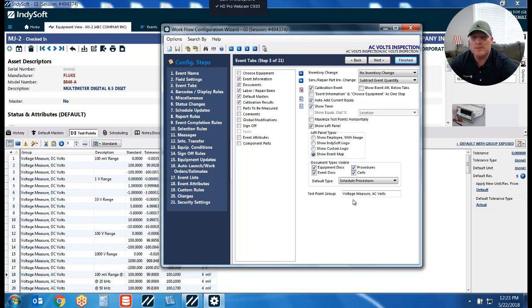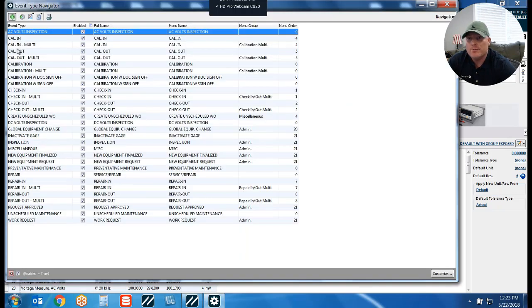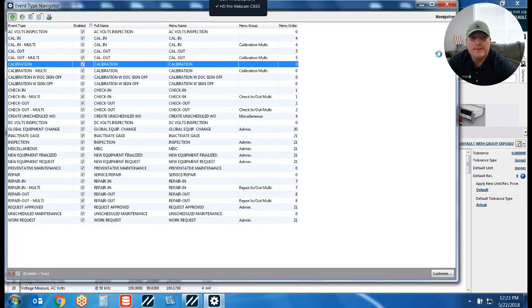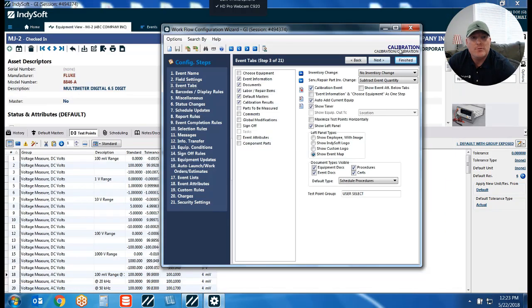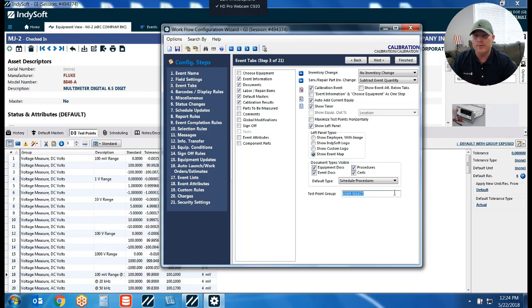Now for the torque wrench scenario, where you just want your user to be able to select and specify which test points they want visible — pulling up my calibration event, you'll see the option we place here is just called 'USER SELECT'. In all caps, we put in the command USER SELECT, and what that does is give the user the ability to choose which group of test points they want when they perform that particular event.